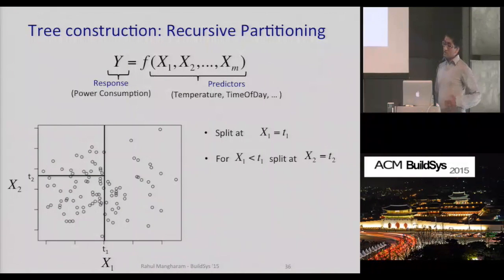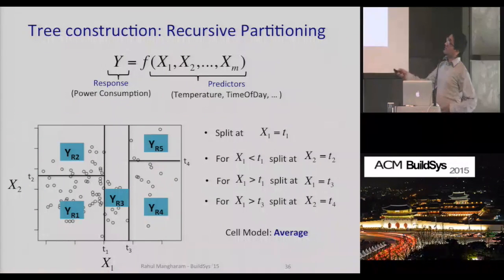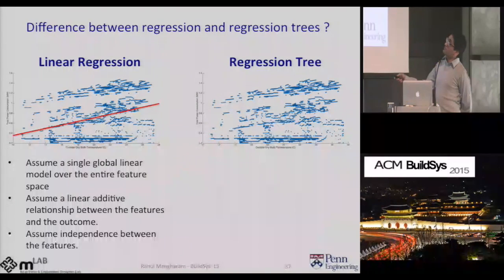We're doing this sort of recursive binary partition because you do not want to use a single linear regression model, as the building has a lot of complexities, interactions, and non-linearities. Essentially, this allows us to figure out the response variables for the different conditions that the building has been through over the historic training period. And this is the problem with just using linear regression, or even polynomial regression, for these very complex and nonlinear systems.